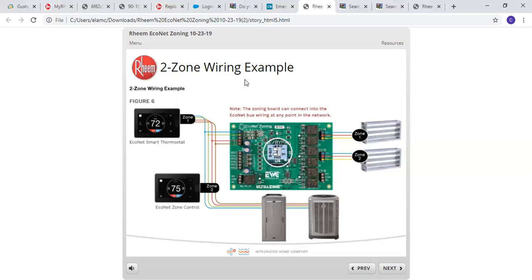So here's an example of our 2-zone wiring. We have our 2 zone dampers here, zone 1, zone 2. We're not using a bypass. So we have our outdoor unit here. We have our 4 wires, E1, E2, R and C, going to the furnace. Then we're daisy chaining out of the furnace going to zone 2 or zone 1, whichever it is. You're going into there, so you're going to daisy chain back out of there to zone 1. So zone 1 in this case is going to be the end of our Econet line here and our outdoor unit here.